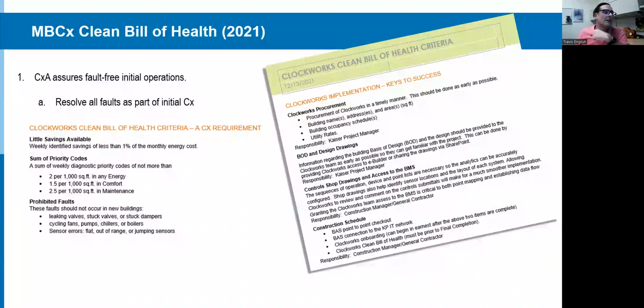We have been successful in including it in the capital. It's actually quite cheap. Not to give away their market numbers, but for deployment of the fault detection software and the first year of service, we've got that down around 5 or 7 cents a square foot. So it's not a big number at all. When we're spending more than $250,000 on controls, our standard says you have to do Clockworks, and at that point it's such a marginal cost that it doesn't get value-engineered out.